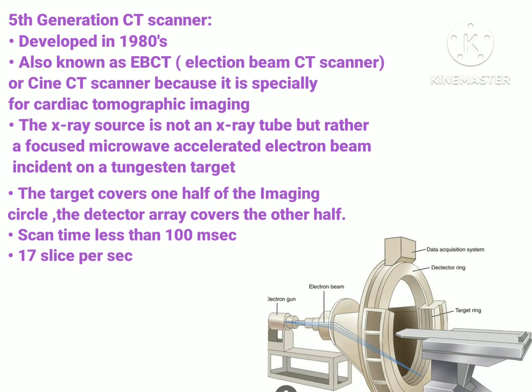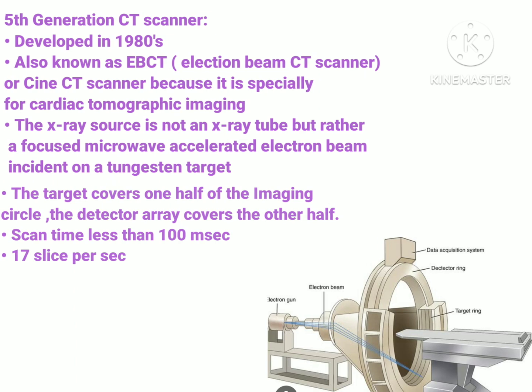The fifth generation CT scanner was developed in the 1980s. It is the first imaging CT scanner also known as EBCT — Electron Beam CT Scanner — or cine CT scanner, because it is specially designed for cardiac tomographic imaging, meaning only the heart can be imaged. The X-ray source is not an X-ray tube but rather a focused microwave-accelerated electron beam incident on a tungsten target. The target covers one half of the imaging circle and the detector array covers the other half. Scan time is less than 100 milliseconds, with 17 slices projected per second.